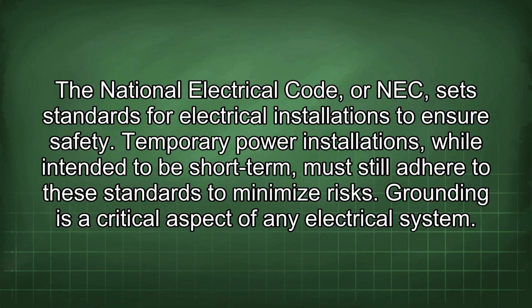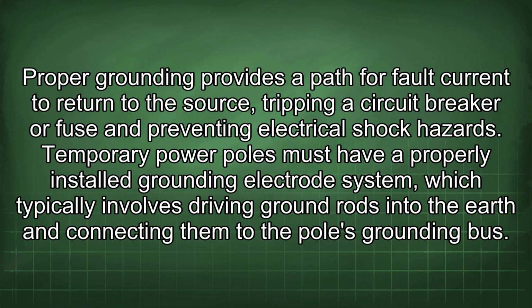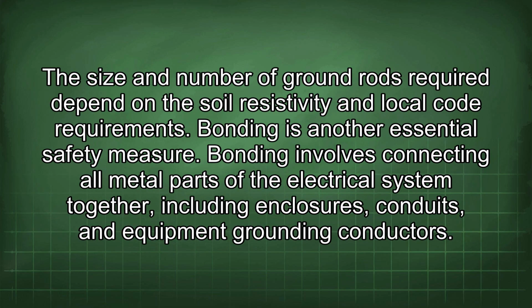Grounding is a critical aspect of any electrical system. Proper grounding provides a path for fault current to return to the source, tripping a circuit breaker or fuse and preventing electrical shock hazards. Temporary power poles must have a properly installed grounding electrode system, which typically involves driving ground rods into the earth and connecting them to the pole's grounding bus. The size and number of ground rods required depend on the soil resistivity and local code requirements.